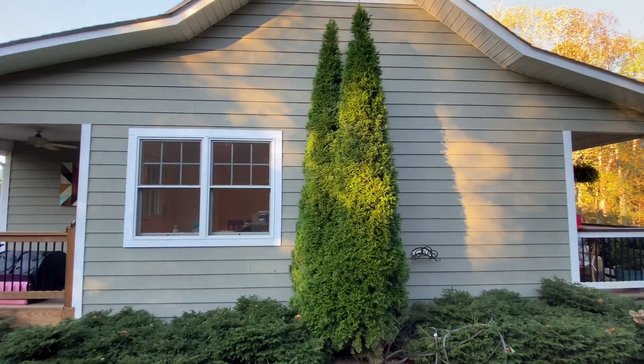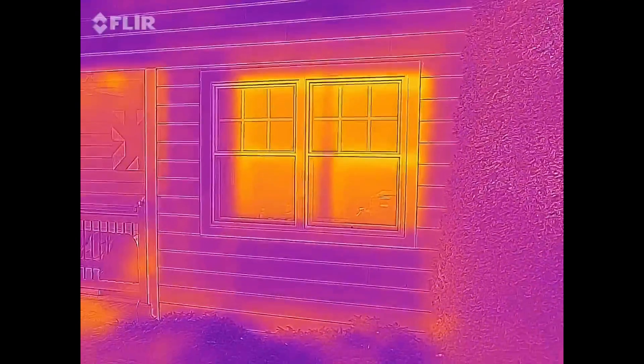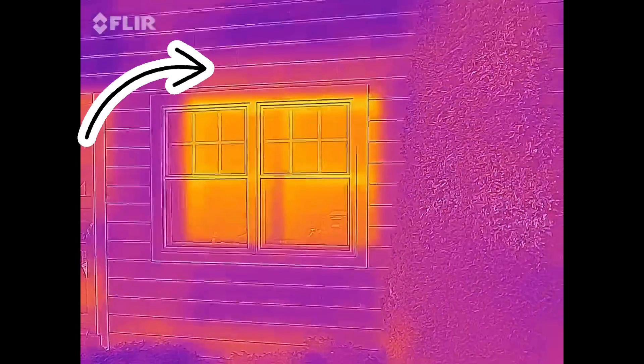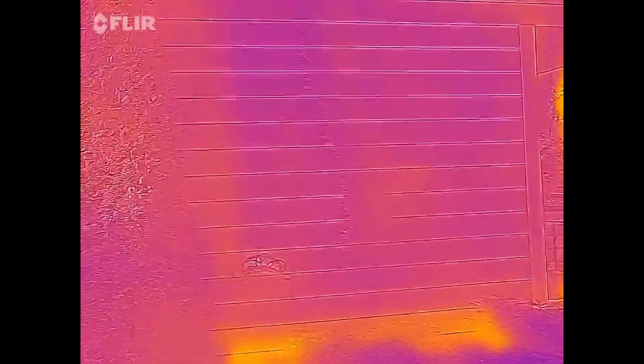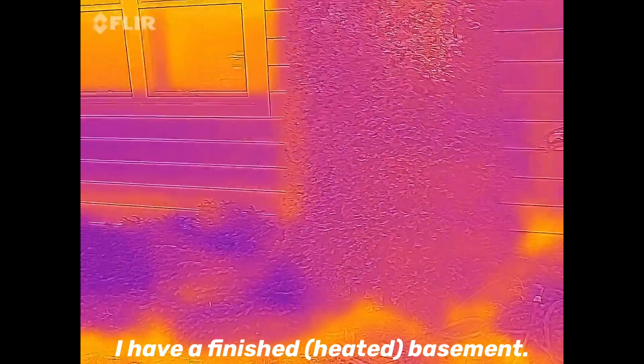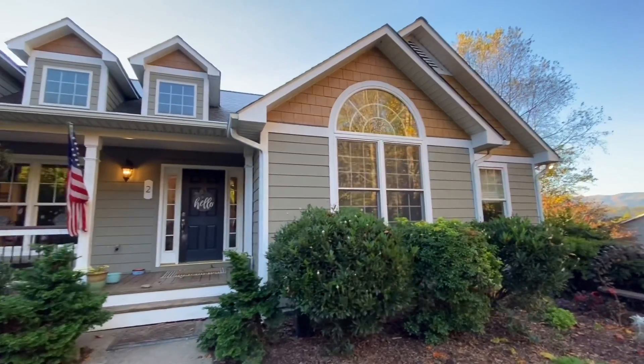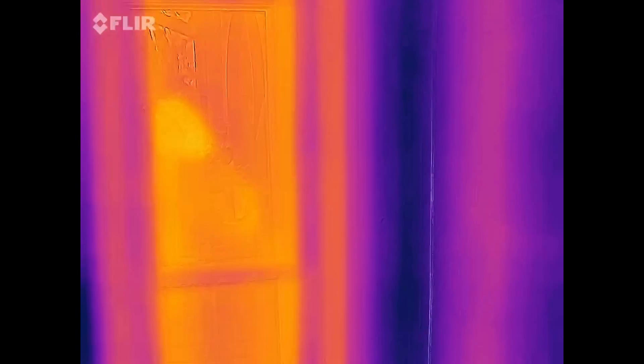Let's start right here — this is just the regular camera. Let's flip over to infrared mode. Well, no shocker here: heat loss through the windows, and I can also see above the window over here where the header is. Here's kind of a weird thing — the major other heat loss area is, of course, studs. I can see those, but the floor system down here at the very bottom — they must not have insulated that band very well. I may be able to get up in the drop ceiling and check that out.